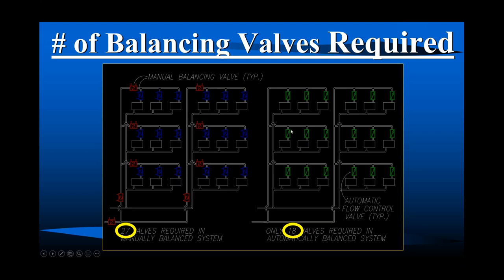Yes, we have to. This is a dynamic device. This is not. Right? All that water would rather go here, right? That's the path of least resistance. There's nothing to push back against it. So this would have to be slightly more closed than that, to make 9 go there, 9 go there, and 9 go there. And that 9 would rather go through this first unit, but you can't. You got to close this down. Make sure only 3 goes there. And I got 6 here. And you have to make sure 3 and 3 go there. That's the balancing process with a manual balance valve.